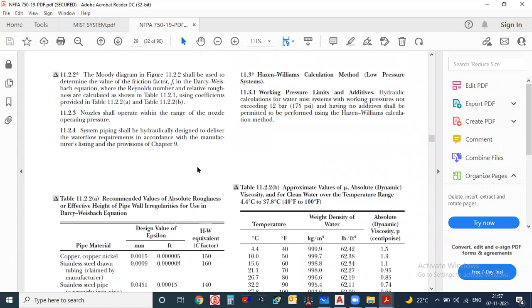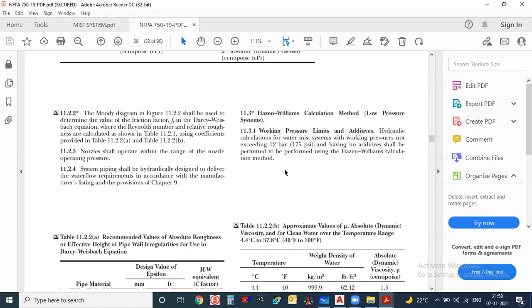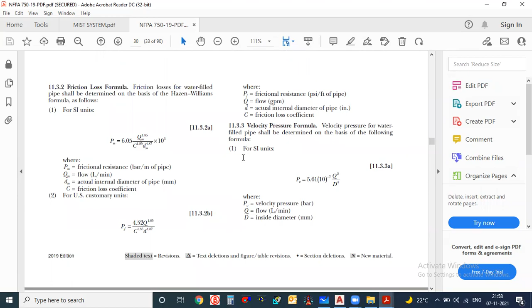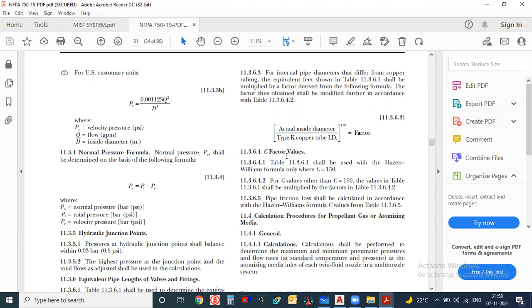And here they have given the Hazen-Williams calculation for low pressure systems. A low pressure system is one whose pressure is 12 bar or 175 psi or below, if you are talking about the mist system. And here they have given some tables. You will see the same method given here, the Hazen-Williams formula. Okay, and the C factor is also given here.